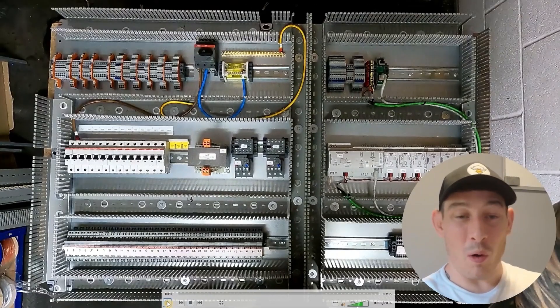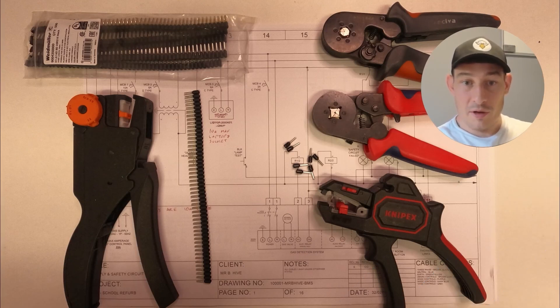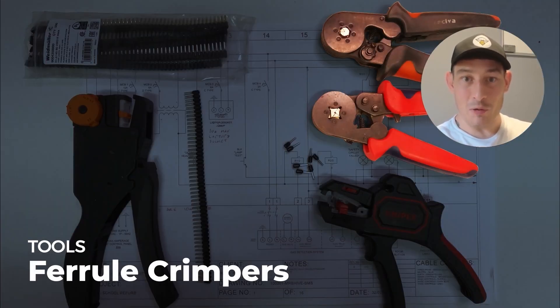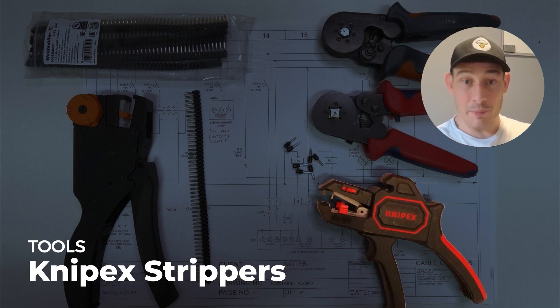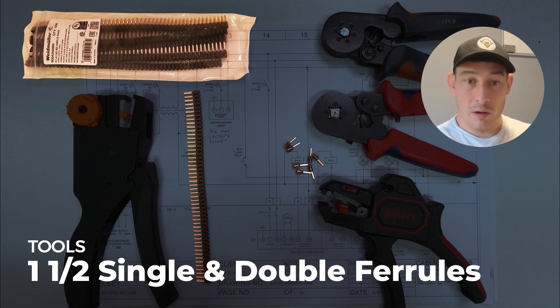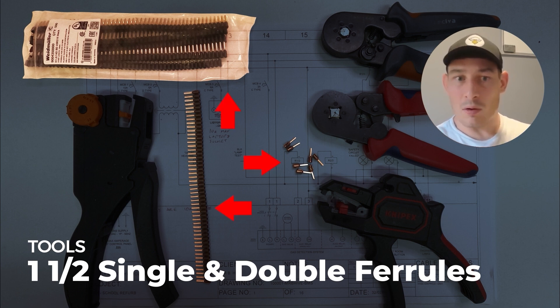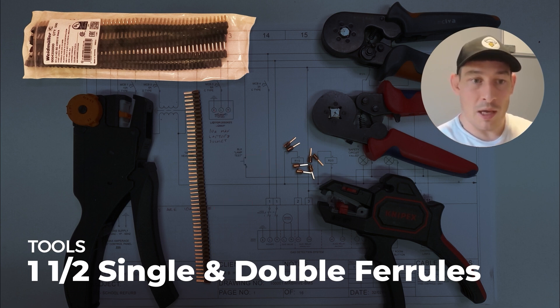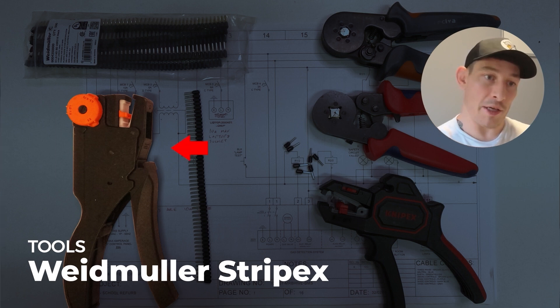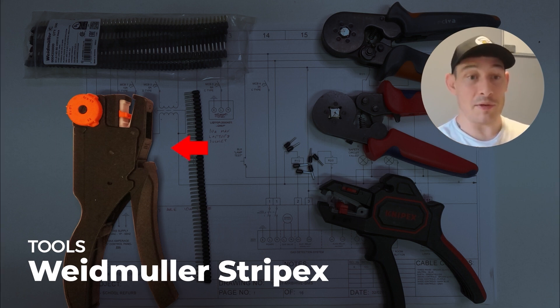Now onto the bulk of the wiring. I just want to show you the tools I use first. Just standard cheaper Amazon ferrule crimpers. I recommend these Knipex strippers — they're really, really good. Only using 1.5 mm cable for 99% of cables in this panel, so 1.5 mm single ferrules, and also using some double ferrules.